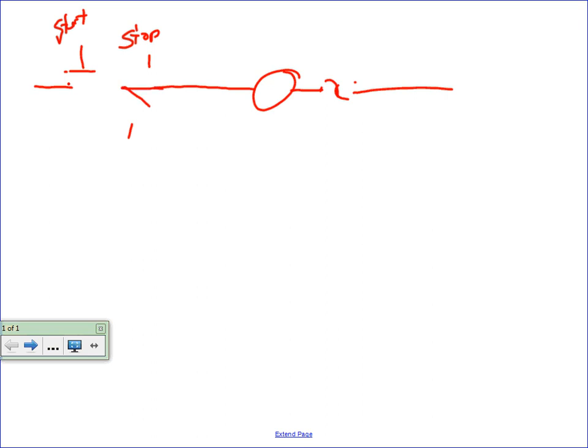basically, here's our stop button, and around this part, we actually use what we call a closing coil, okay? So you push the button down, it completes the circuit, the coil closes. So we use an aux contact off that coil. As soon as that closes, this closes. Now when you release the start button, the circuit bypasses it and it runs. You lose power, the coil drops out, this opens back up. Now when the power comes back on, the system will not automatically start up.